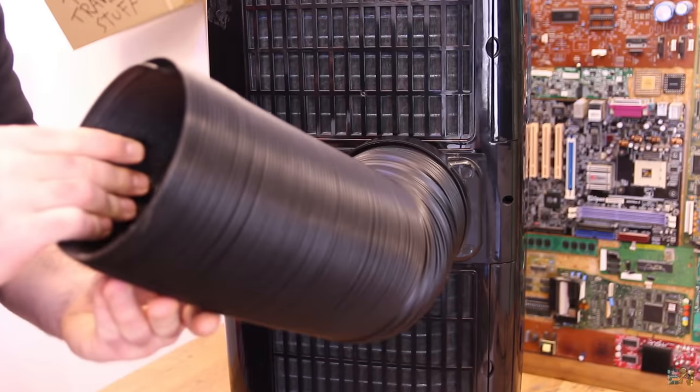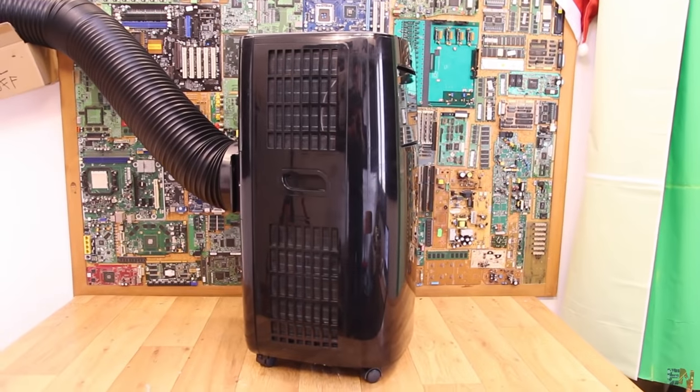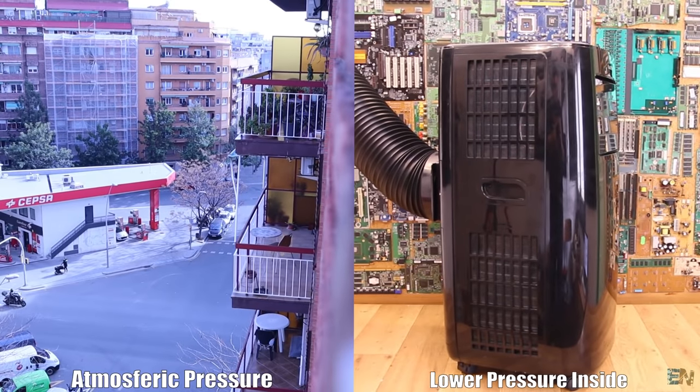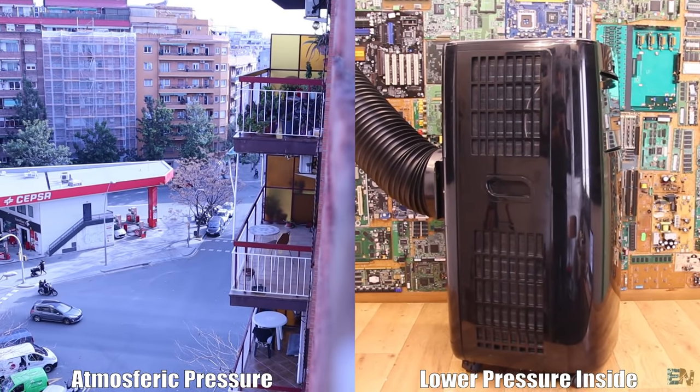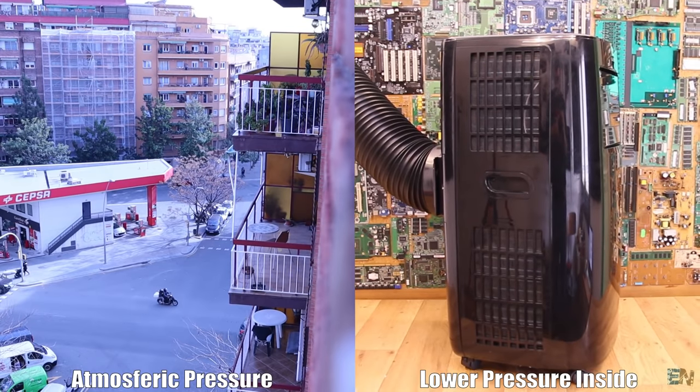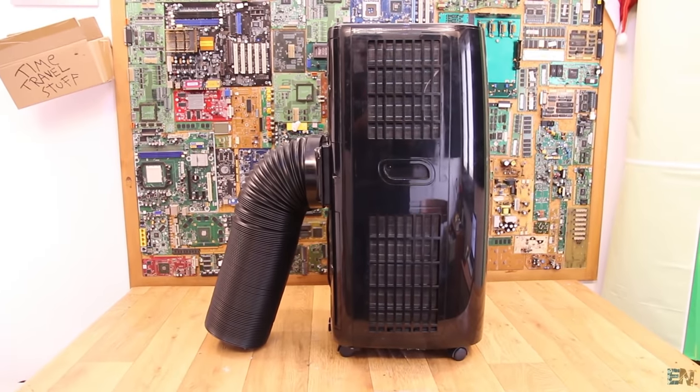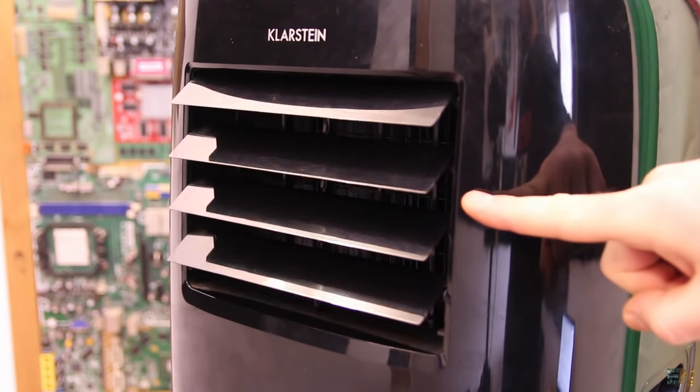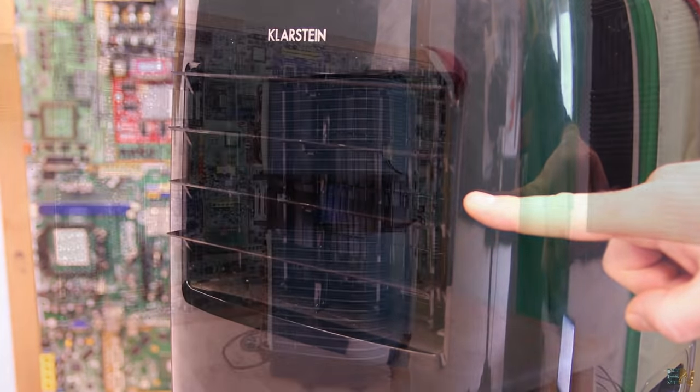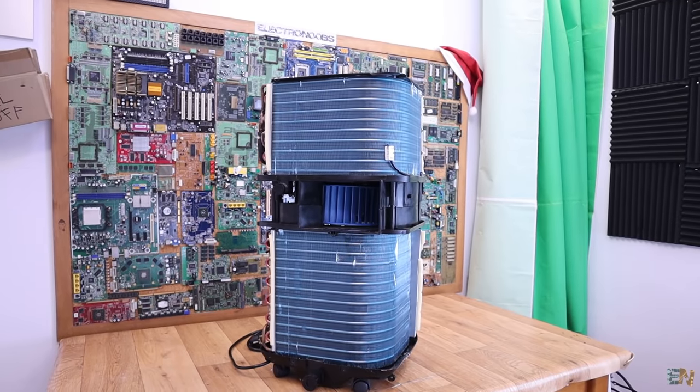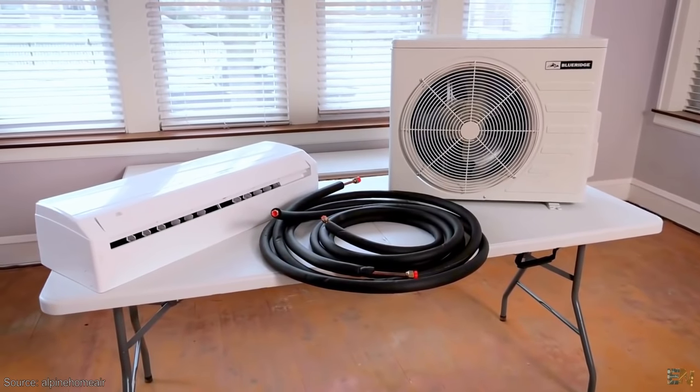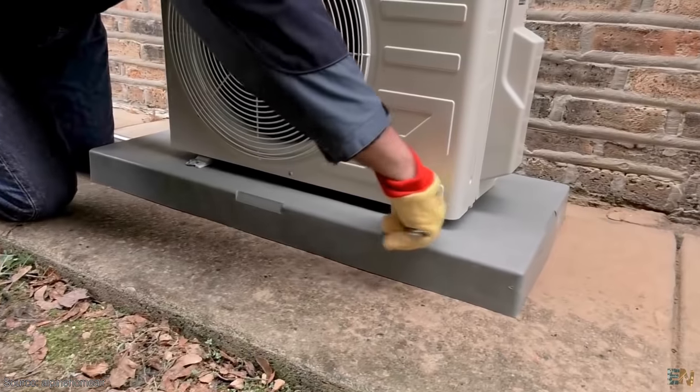And there is more. Since the condenser is sucking air from the room and then pushing the hot air outside of this room through this tube, that means that the overall pressure inside of my room is lower than the pressure outside. So since the atmosphere wants equilibrium, in some way the hot air from the outside will find its way back into the room. The best way scenario is to have the evaporator inside of the room and the condenser on the outside of the room.